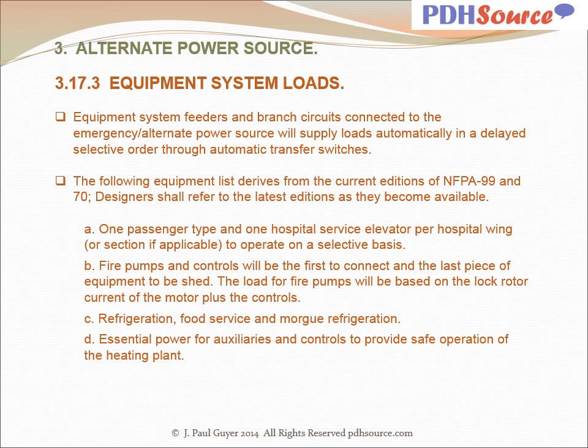One passenger type and one hospital service elevator per hospital wing or section, if applicable, to operate on a selective basis. Fire pumps and controls will be the first to connect and the last piece of equipment to be shed. The load for fire pumps will be based on the locked rotor current of the motor plus the controls. Refrigeration, food service, and morgue refrigeration. Essential power for auxiliaries and controls to provide safe operation of the heating plant.